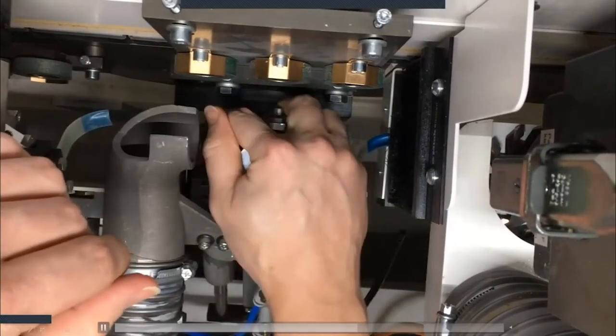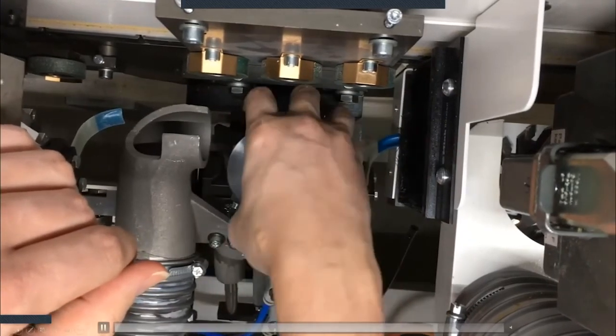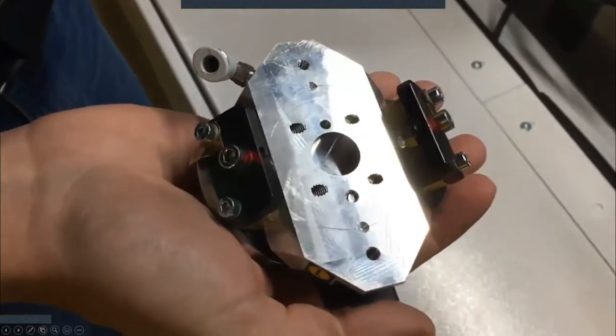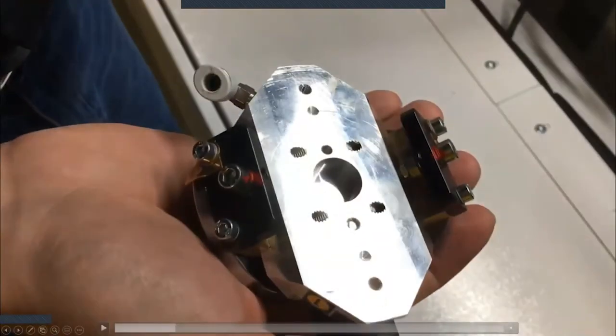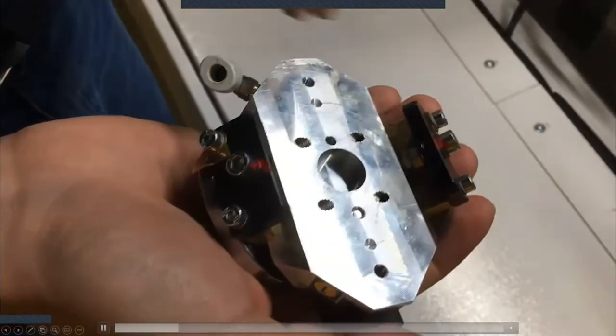Here you can see I'm going to remove this scraper head out. I'm going to push, twist, and slowly wiggle until I can freely pull the scraper head out. Once I get it out, I want to inspect the mating surface. I don't want any damage, any dings, any rough spots. These will wear over time. It is aluminum, so I ask that you take very good care of this area.